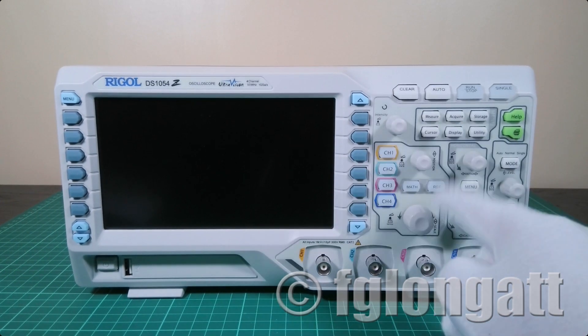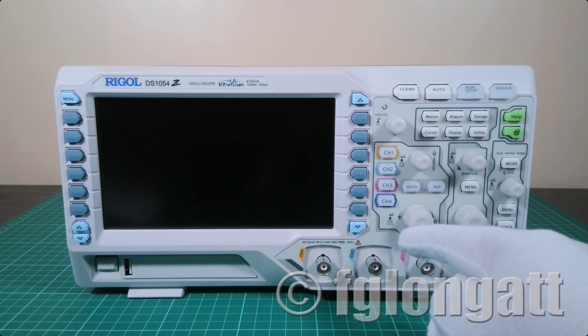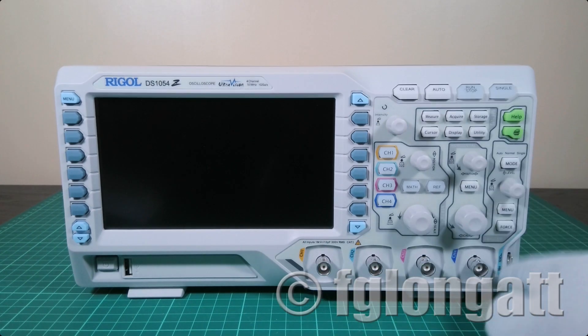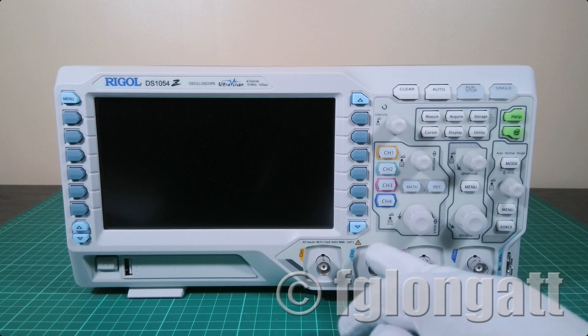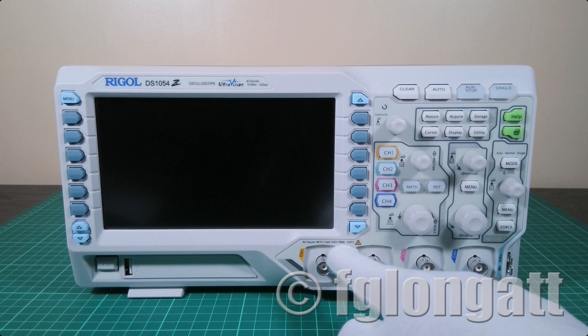The vertical scale of this device ranges from 1 mV per division to 10 V per division. As you can see, you can plot four different channels simultaneously on the screen. This is one of the advantages and one of the reasons we have this device at the lab, since electrical power systems are traditionally three-phase systems. Using four channels, we can record four different signals at the same time, and the maximum voltage for each channel is 300 volts RMS.